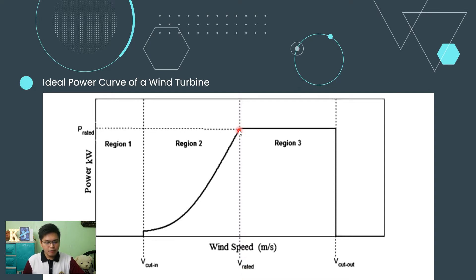In the high-speed region, the turbine power is limited so that the turbine and generator are not overloaded and dynamic loads do not result in mechanical failure. To protect the turbine from structural overload, it should be shut down above the cut-out speed. This paper focuses on the moderate-speed region where the maximum power point tracking algorithm is needed.